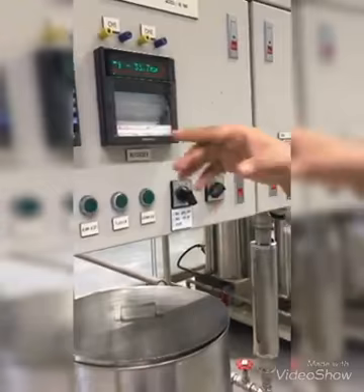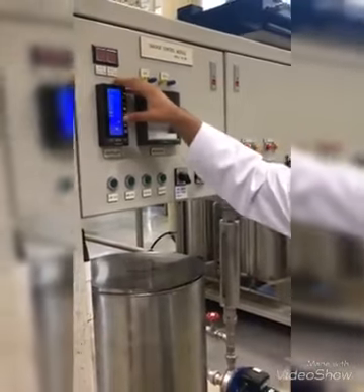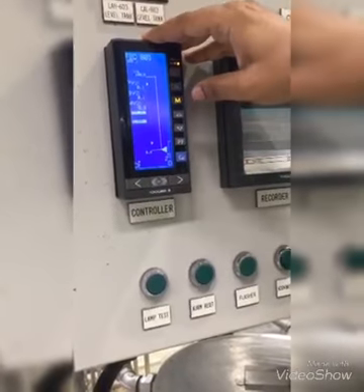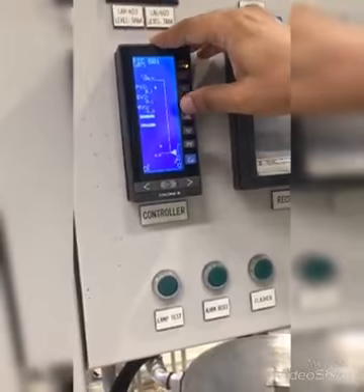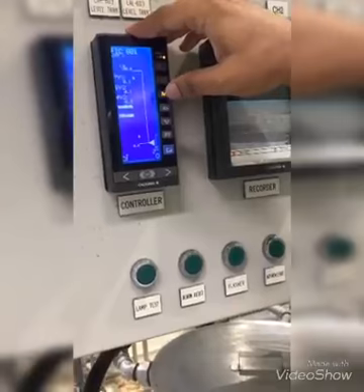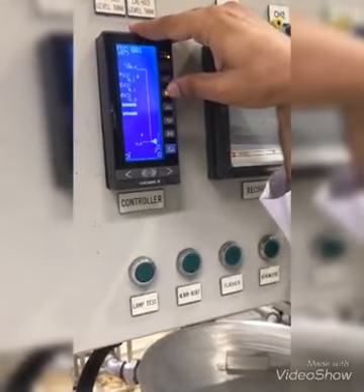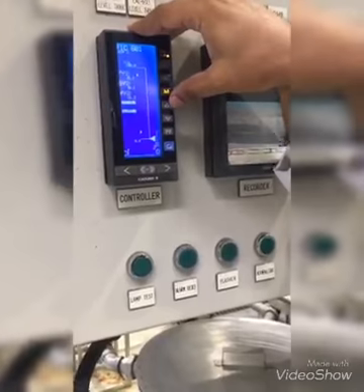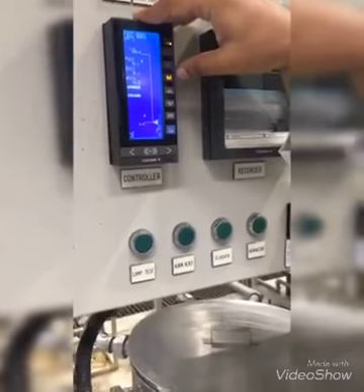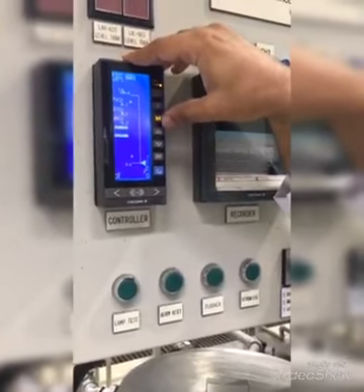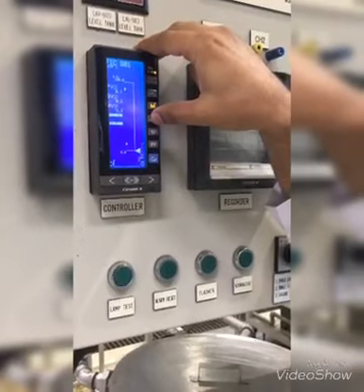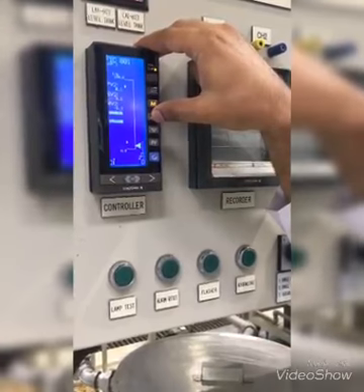Okay, right now we need to make sure that single flow loop. Right now we are going to do the tuning of flow indicator control. We are going to insert the setting point values. For example, to 100%. We need to make sure the mode is in manual in order to manipulate the values. We increase, for example, this one to 10.